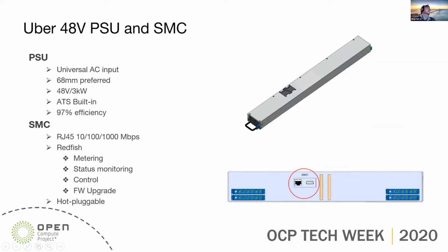It's a universal AC input. We use that only for Uber. We prefer 68 millimeters in order to put 6 power supplies in 1U into the 19-inch rack.